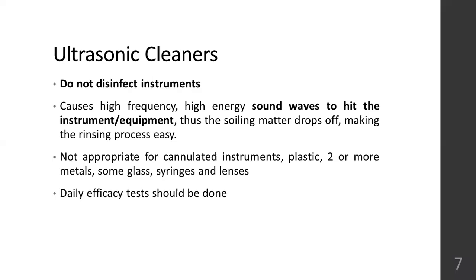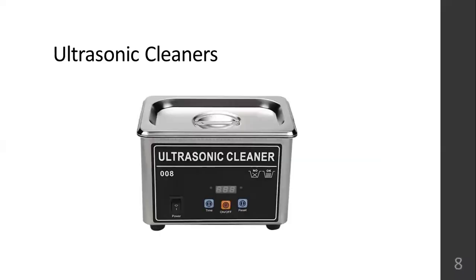Any instrument that is cannulated, which has hollow bores, plastic, made up of an alloy of two or more metals, glass, syringes, lenses, for these kinds of instruments ultrasonic cleaners are not used. A daily efficacy test should be done when you're using ultrasonic cleaners. This is how an ultrasonic cleaner looks like. They don't disinfect, they just ensure that soiling and any organic compound on the instrument falls off.